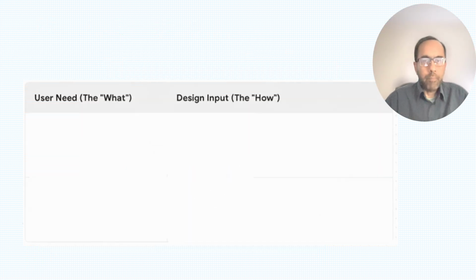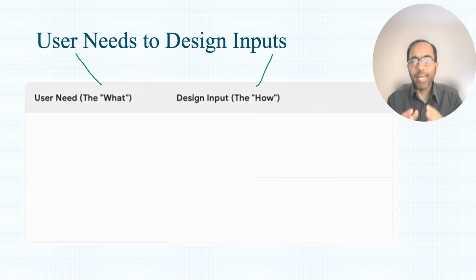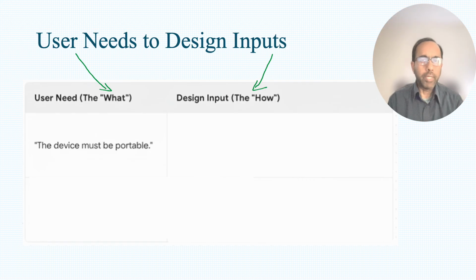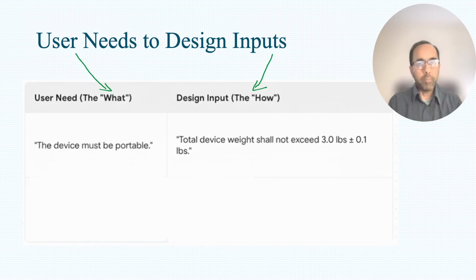This is where the magic really happens, the fun happens. This is the translation from user needs to what we call design inputs. Now, you may have heard the term system requirements. Design inputs are system requirements. So there might be a user need that says the device must be portable. That is subjective, right? High level requirement. Now we need to translate that into a design input, something that's concrete, measurable, and you can verify with objective evidence. So "portable" becomes the total device shall not weigh more than 3 pounds, plus or minus a tolerance maybe.